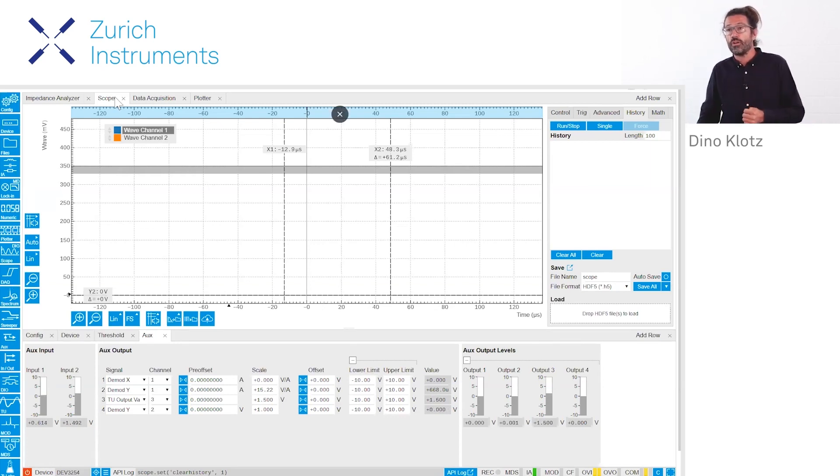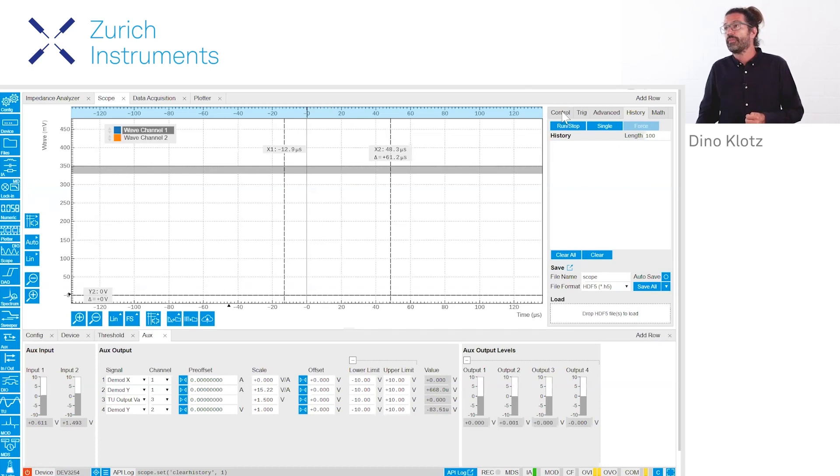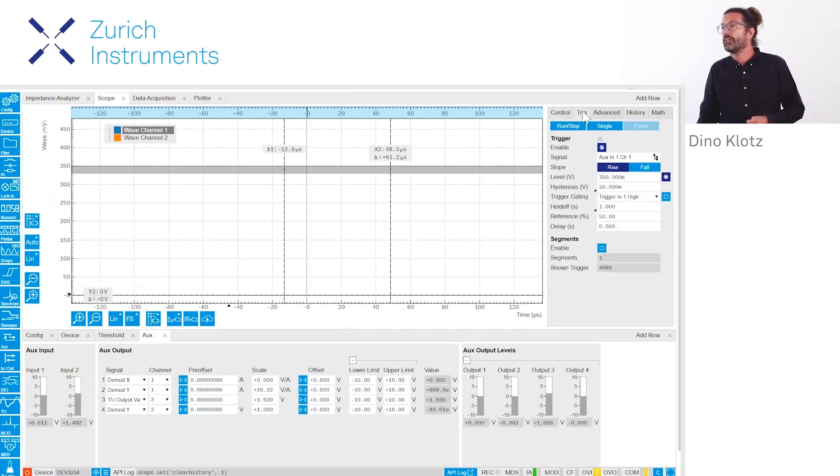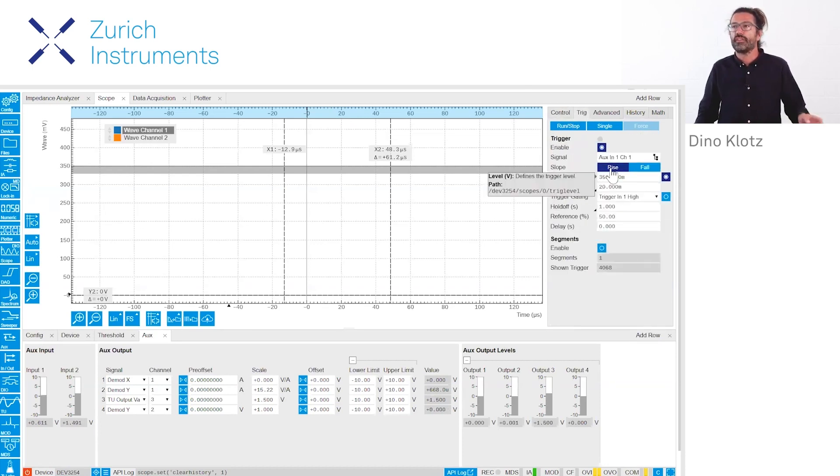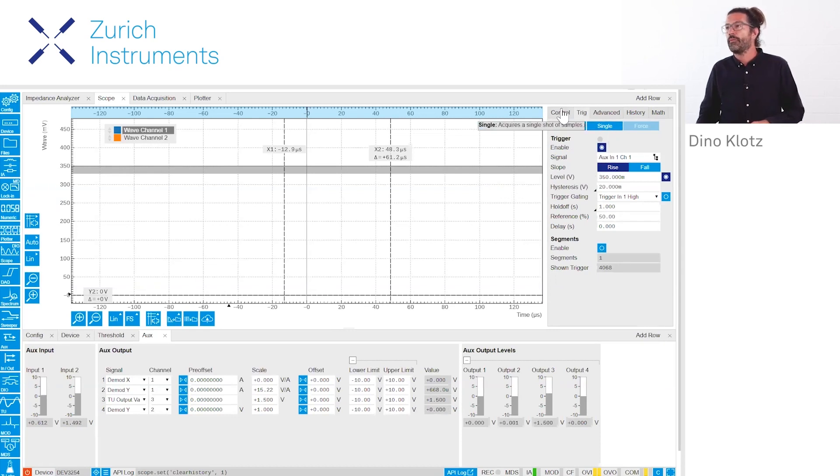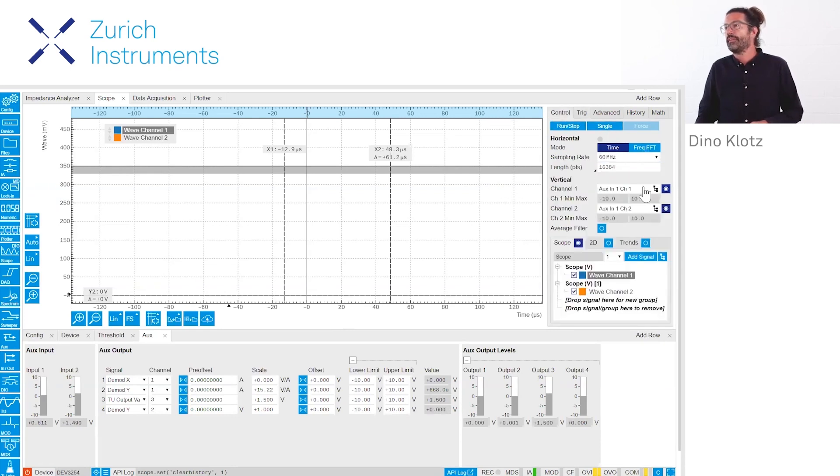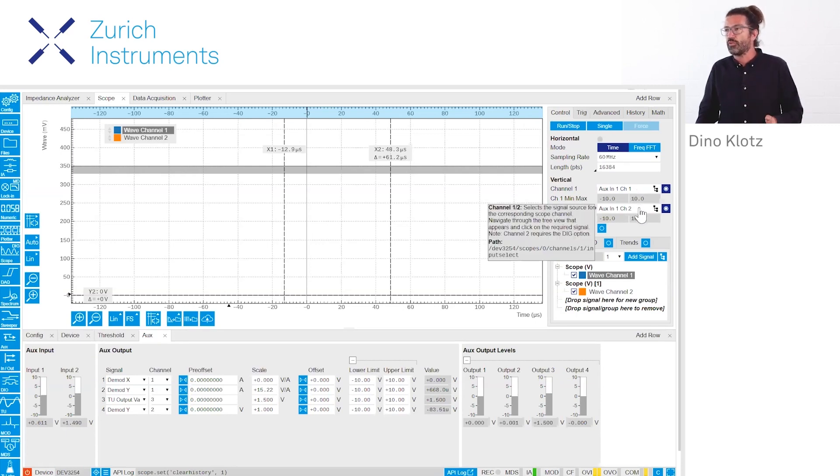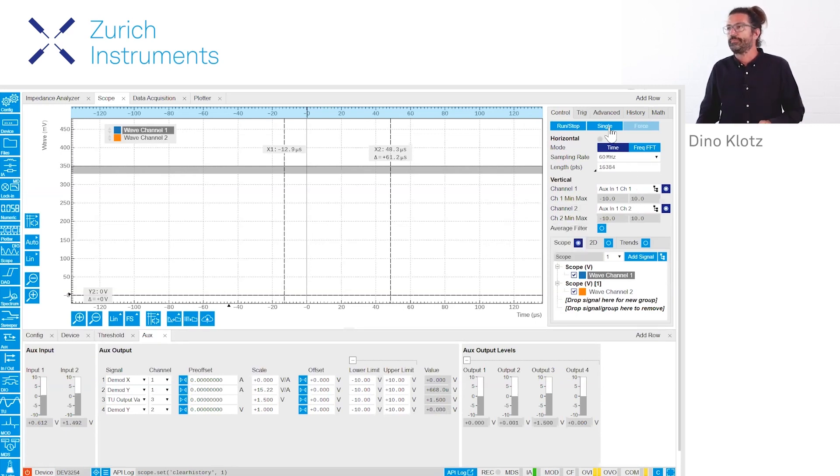Now we want to look at here in the scope how well does that work. We're triggering at a rise time here and we're comparing the aux in one and the aux in two, so that's the sensor signal and that's the drive signal.